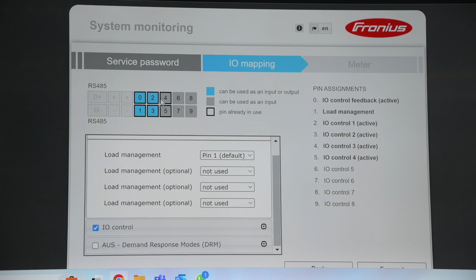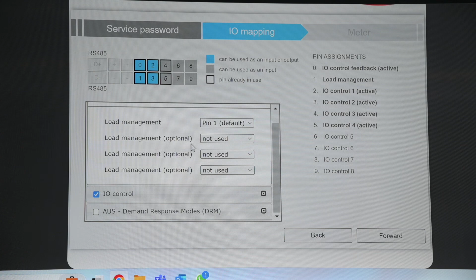Next is the I/O mapping. This is where you have your inputs and outputs that you want to trigger separately. So if you had load management, this is when you are triggering a separate relay to open with PV surplus that's available. You can then define what pins it is on the I/O block. So there's our RS485 connection block. We can then assign which pins it is assigned to, as well as our I/O controller itself. We can define which pins we are utilizing.